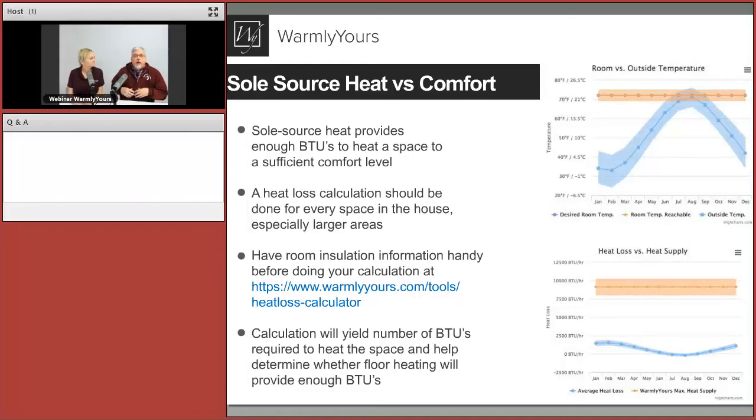And will our product supply that number of BTUs or more? Because if it's the same amount or more, we know that you're going to be comfortable 365 days a year. If it says you need 2,000 BTUs and our product can only give you 1,800 BTUs, that means your product will probably be the sole source of heat on all but 1 or 2 days. The 1 or 2 coldest days of the year, you may have to turn your towel warmer on. There you go.